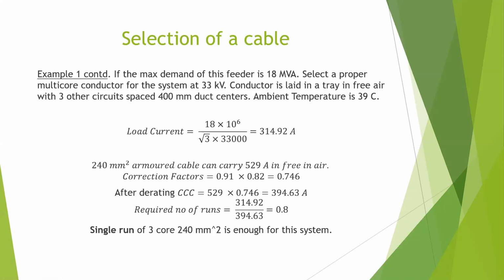Duct centers means usually we have HDPE duct around this conductor. So we are going to get the space between two duct centers for this design. And ambient temperature is also given, 39 Celsius. And you can easily calculate the load current.